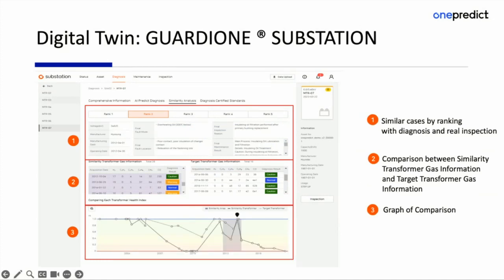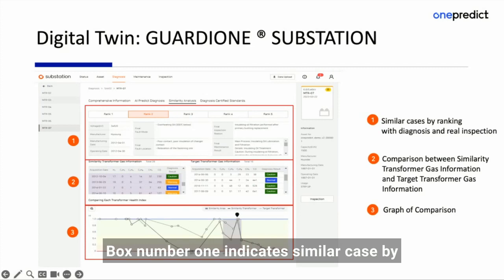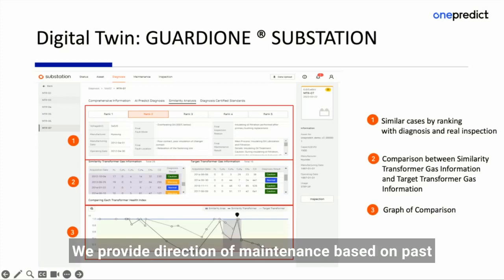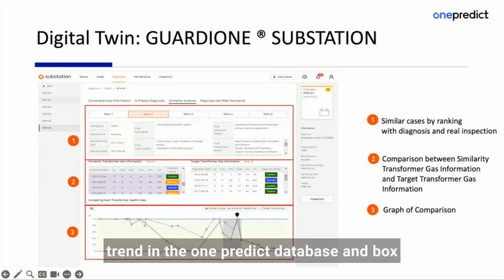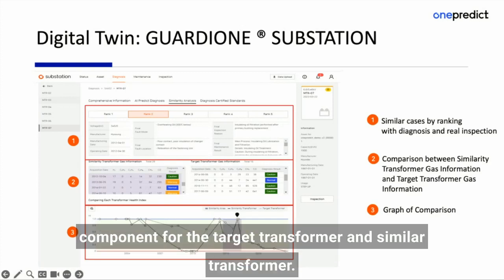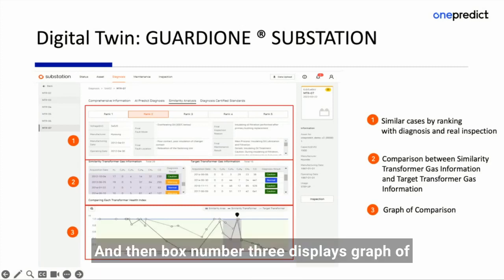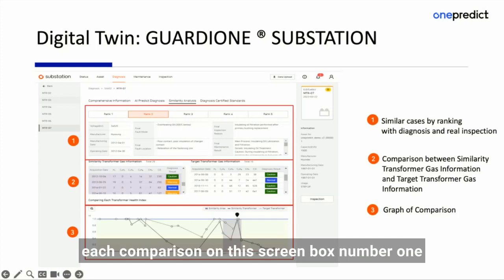On this screen, box number 1 indicates similar cases by ranking, with diagnosis and its real-life inspection. We provide direction of maintenance based on past and future health of transformers with similar gas trends in the OnePredict database. Box number 2 shows the gas value of each chemical component for the target transformer and similar transformers. And then box number 3 displays a graph of each comparison.